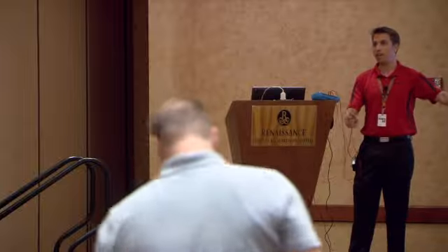You can use this to measure the voltage that's coming into the meter, and we're going to use that as a calibration point. Typically, if you have a reference generator, it's going to tell you exactly what your voltage is so you don't have to touch it. That's ideal. It's going to force the voltage and make sure that it's constant and stable, so you won't have to measure it like this. But for these purposes, we need to at least know what we're dealing with at the voltage level.